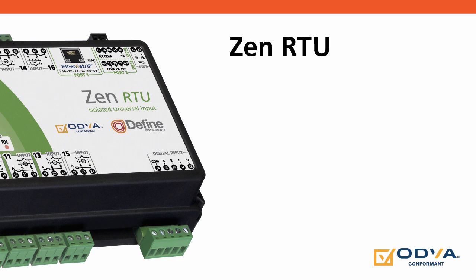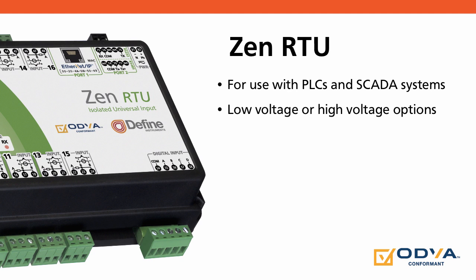The Zen RTU is primarily designed for use with PLCs and SCADA systems. It is available with a number of different options. It comes with a low voltage power supply for direct connection to 24 volt DC systems. Or else it comes with a high voltage power supply which lets you plug it into your mains supply, and it is variable over the whole range of mains voltages.